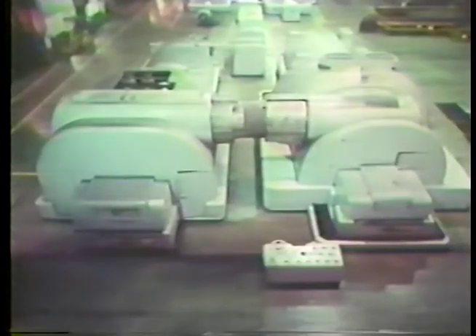As the furnace cools, so do the tubes in the superheaters, reheaters, and other steam-carrying components. To prevent an accumulation of water in these areas, the operator opens drains to provide a flow path for the water. It is important to prevent water accumulation in steam-carrying components to minimize water hammer and the carryover of water droplets into the turbine.